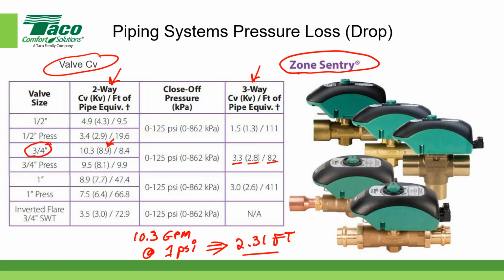And so a PIC valve is kind of an odd thing because the actual characteristics of the valve change as the inlet pressure increases or decreases. But if you had the maximum opening of the valve, the CV would relate to the valve as if it was 100% open. Yep, makes sense. Okay, any other questions? Nope, move on.